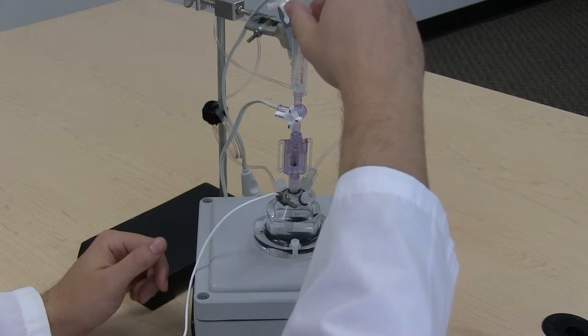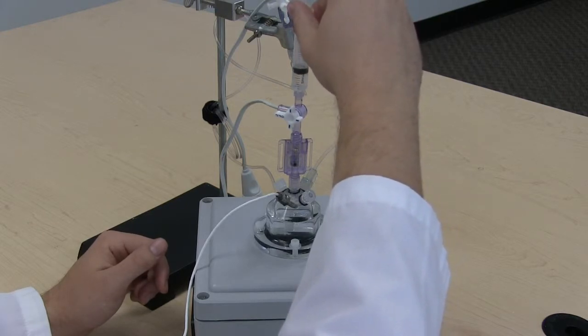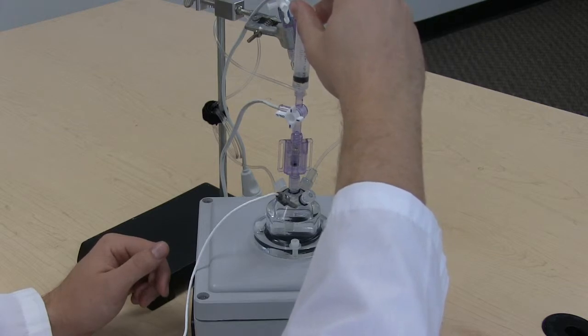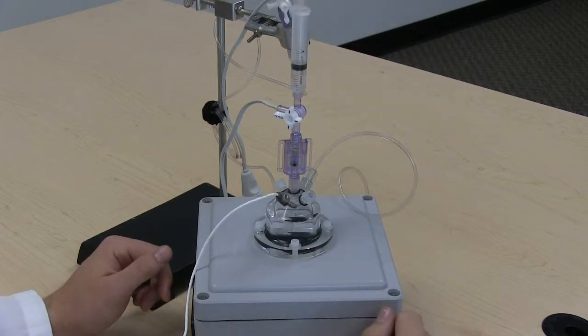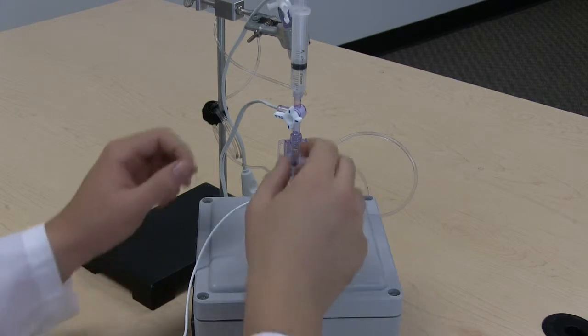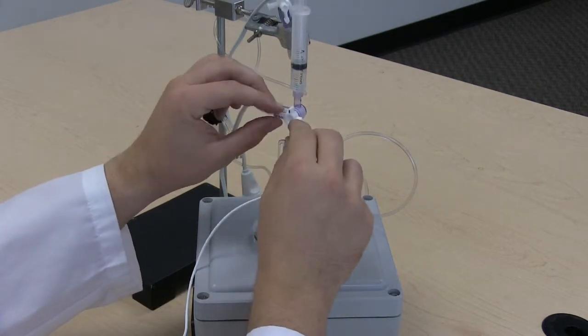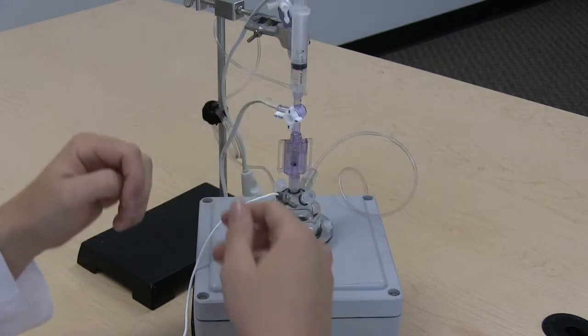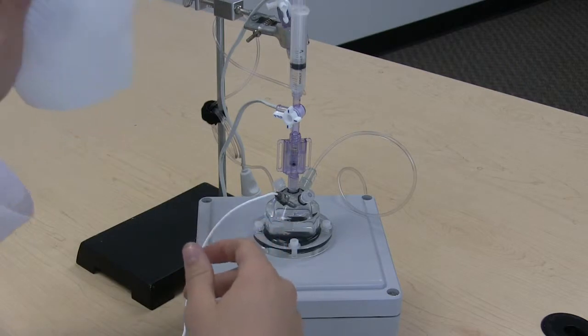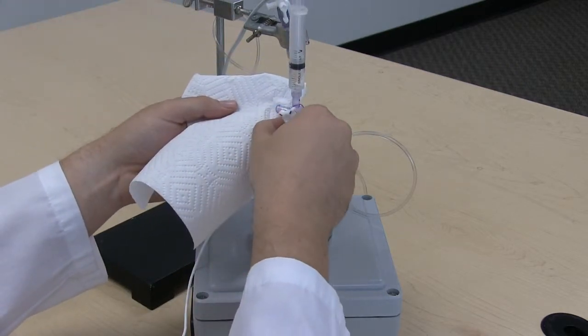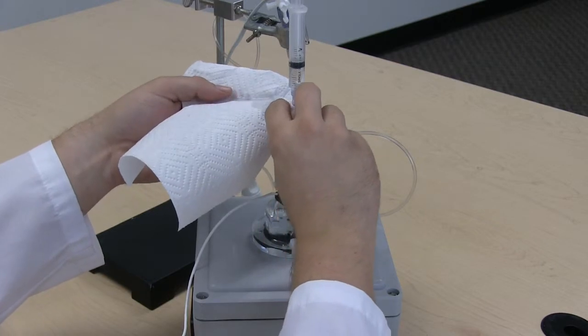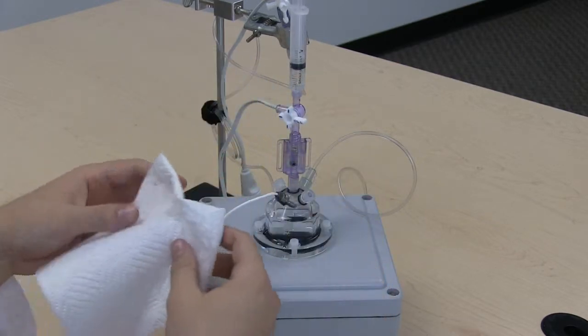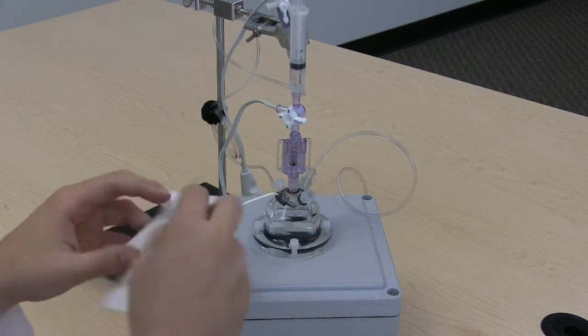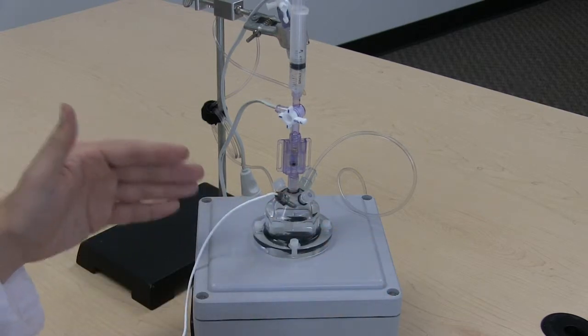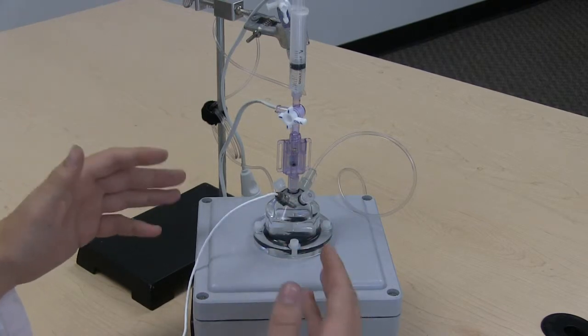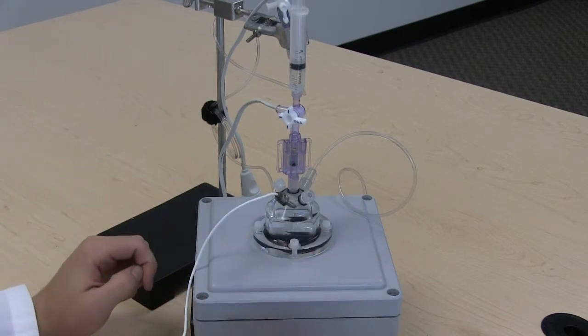We'll then push the water back into the system until we can feel significant resistance, and then we'll allow the syringe to return to its natural position. At this point, we'll want to turn this lock to allow the pressure inside the chamber to equalize with ambient. You'll want a paper towel ready. We'll turn the valve around and catch that water. The same process should be repeated for every pressure transducer or catheter that's attached to the system to ensure that there are no bubbles before a test is started.